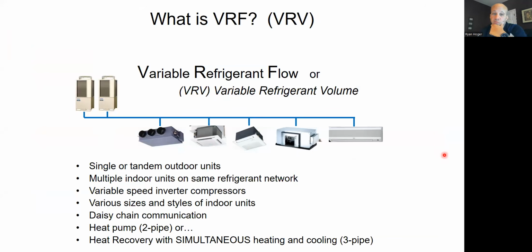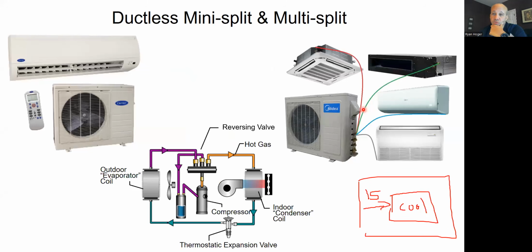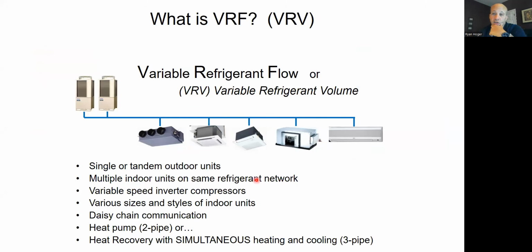I can also have more than like 4 or 5 indoor units. Like these other ones, 2-ton, 3-ton, 4-ton. Maybe somebody makes a 5-ton system. That's probably it. Here, we're probably talking usually 6 tons and up, but there are some models that are 3, 4, 5 tons, but usually 6 tons and up. You might have 10, 12, 15 tons of cooling capacity here, feeding all these indoor units, right?